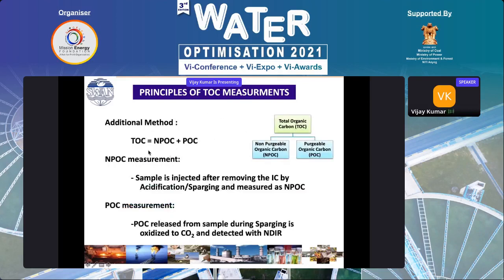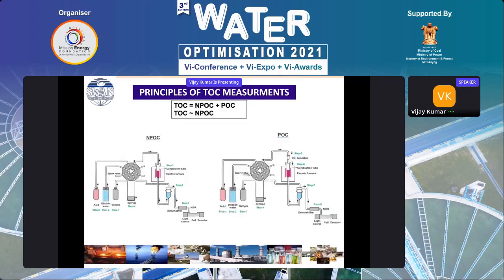Another method is NPOC, or POC. Basically, here there is one step only. You remove IC and measure the balance sample as TOC. But while you are removing IC, you are purging the sample, so if any purgeable organics are in the sample, they go out. That's why POC and NPOC have been defined. The balance sample is NPOC. Here we don't use the reaction vessel. We use the syringe itself as a reaction vessel. The sample is collected, then acid is added automatically, and the IC converted to CO2 is purged out. Then the balance sample is injected into the catalytic conversion port, where it converts to CO2 and is measured as NPOC.